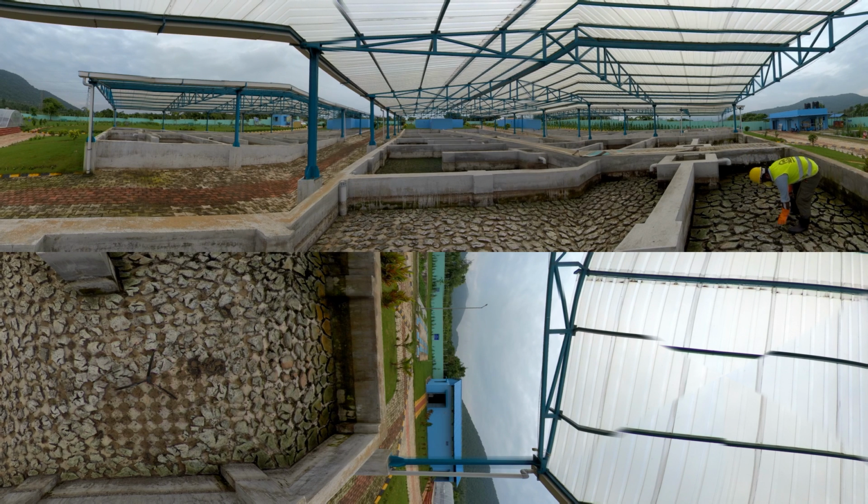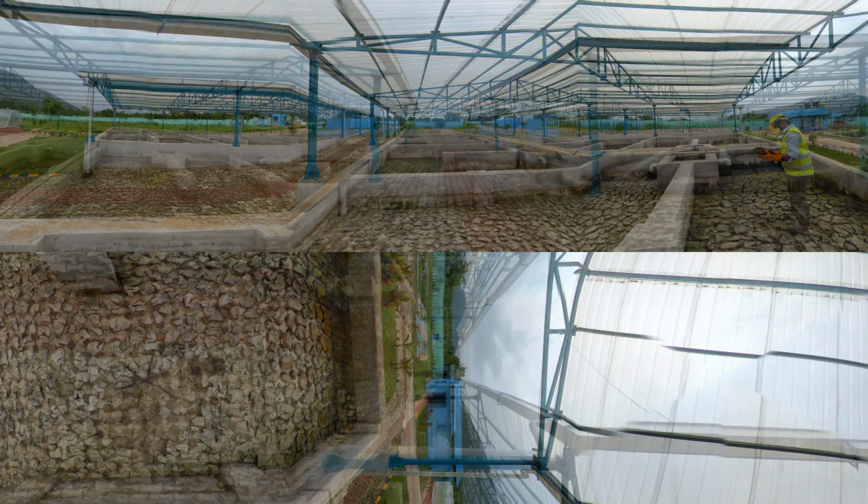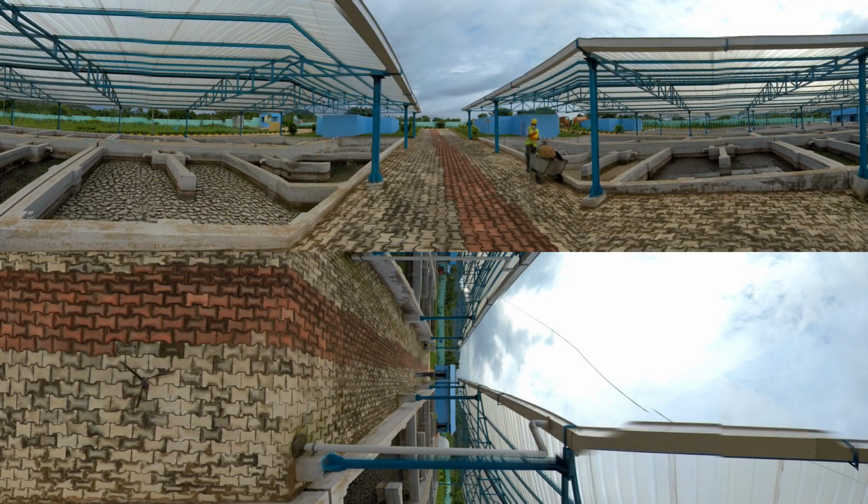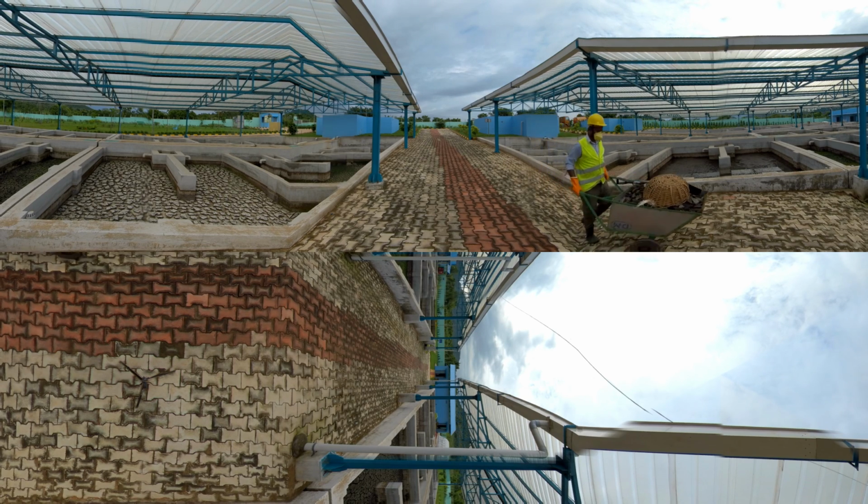Every day you should check if the sludge in any of the beds is visibly dry. Usually, it must be dry within 12 to 15 days of application. The sludge is ready to be collected when it starts to curl up. Pick up the dried sludge. Remove the excess sand by gently tapping it and deposit it in a wheelbarrow. Transfer the dried sludge to the storage facility.